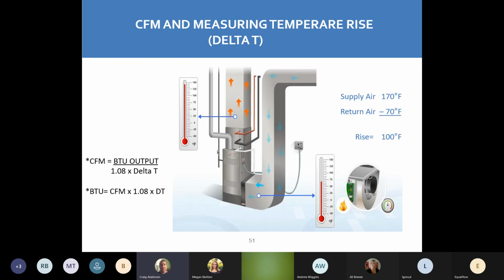Temperature rise, just like if we're starting up a gas furnace, we're looking at temperature rise in our air conditioner. We're looking for the TD between the return and the supply. Let's make sure we're in the parameters of what it's asking for on that unit, that SEER level. So this is why we need some pocket thermometers. I always say 2, so you're not taking from your supply, taking your return, waiting for it to cool down to get the temperature and moving it back and forth. 2 pocket ones, throw them in. Let's sit there and see what it's doing. So static, temperature rise, another big thing in our air conditioning systems and our heating.